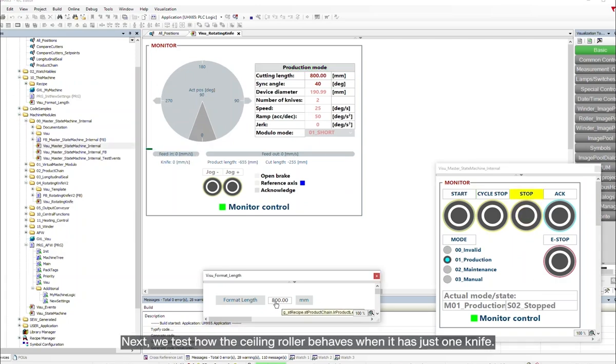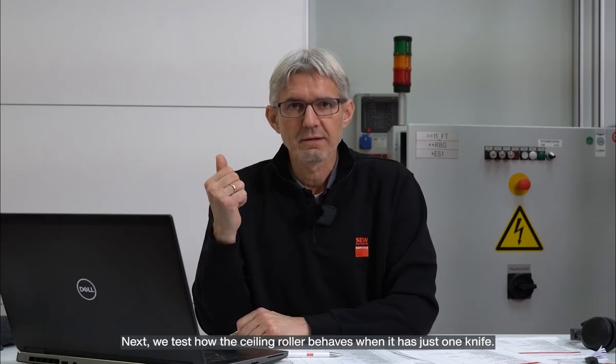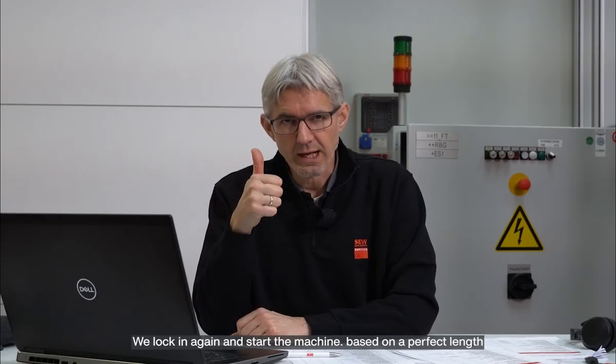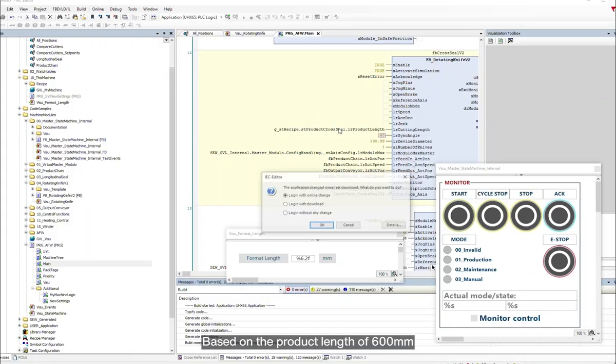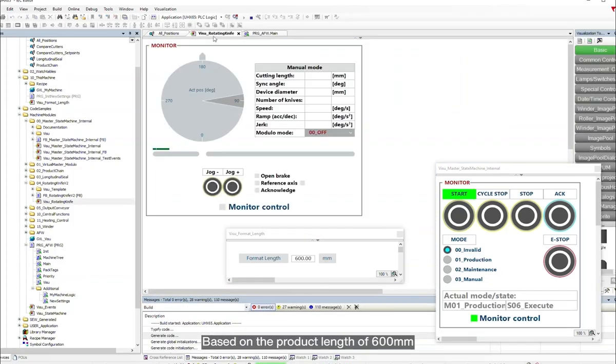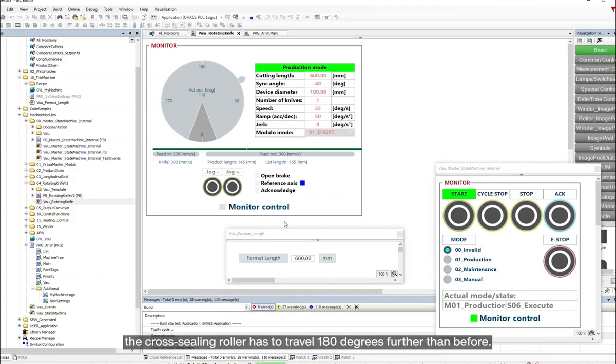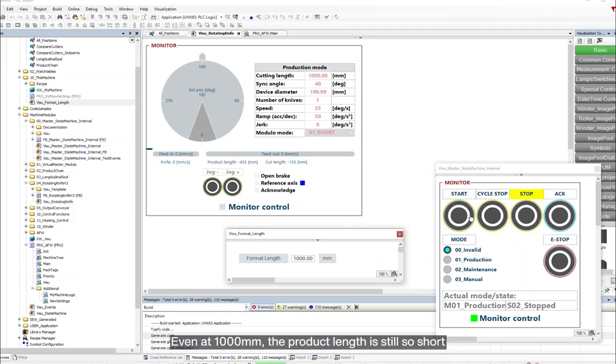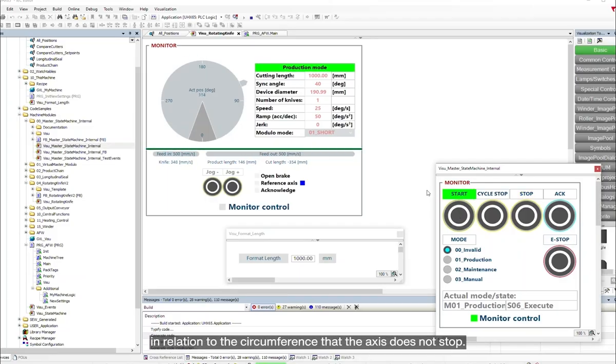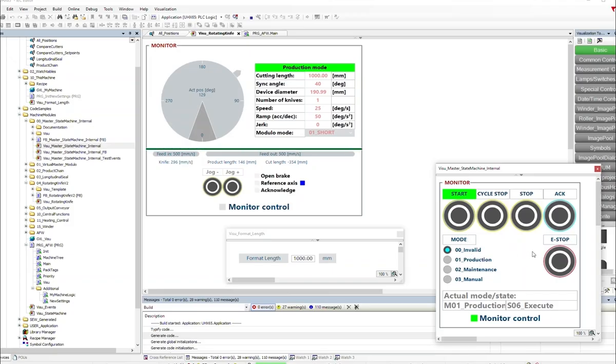Next, we test how the sealing roller behaves when it has just one knife. We log in again and start the machine. Based on the product length of 600 millimeters with just one knife, the cross-sealing roller has to travel 180 degrees further than before. Even at 1000 millimeters, the product length is still so short in relation to the circumference that the axis does not stop.